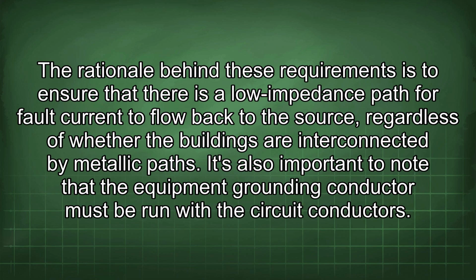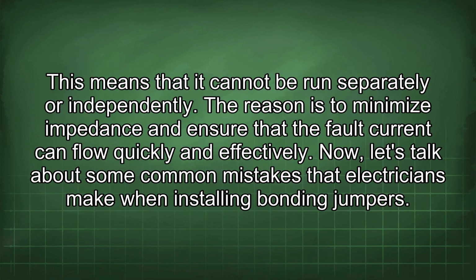The rationale behind these requirements is to ensure that there is a low impedance path for fault current to flow back to the source, regardless of whether the buildings are interconnected by metallic paths. It's also important to note that the equipment grounding conductor must be run with the circuit conductors. This means that it cannot be run separately or independently. The reason is to minimize impedance and ensure that the fault current can flow quickly and effectively.